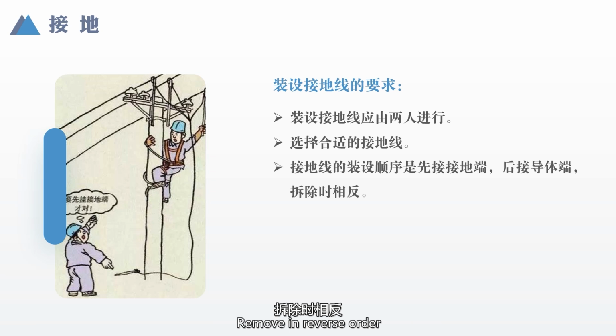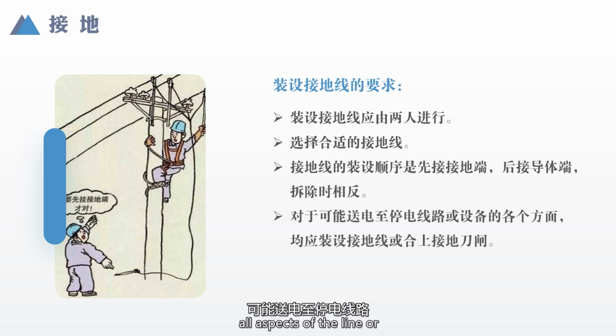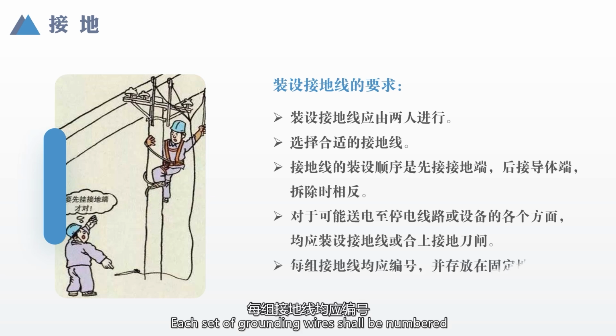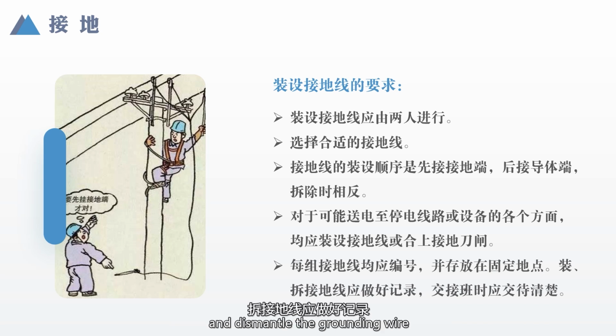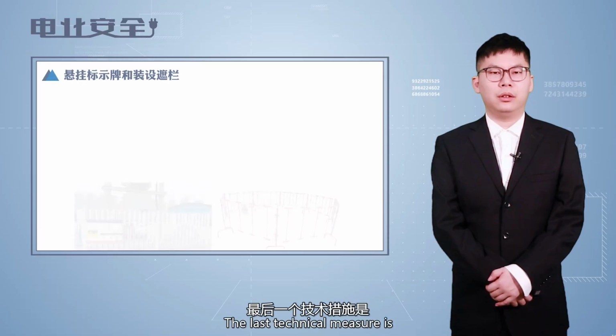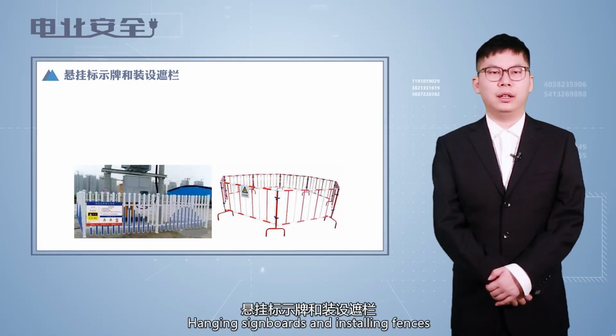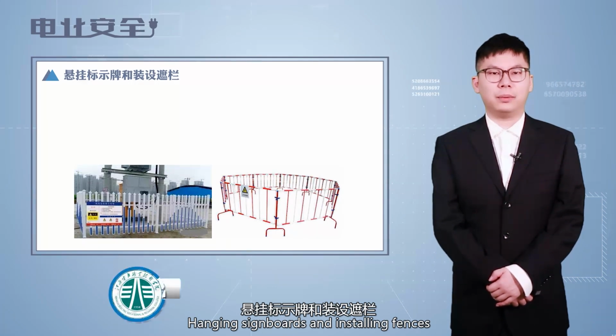Remove in reverse order. For all aspects of the line or equipment that may be fed to an outage or equipment, grounding conductor should be installed or the grounding knife gate closed. Each set of grounding wires shall be numbered and stored in a fixed location, and dismantling of the grounding wire should be recorded. Shift handover should be clearly explained. The last technical measure is hanging signboards and installing fences.